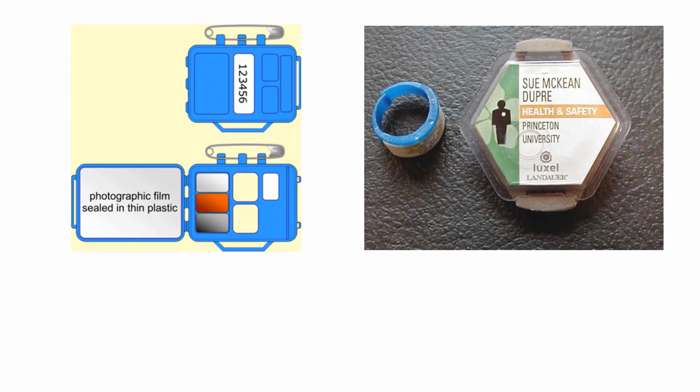Commonly in medical imaging, two badges are worn. For most techs, they will wear a normal dosimetry badge. Nuclear medicine techs, who work up different procedures using ionizing radiation as a radionuclide, will wear a ring badge as well because they are holding the radionuclide in a syringe in their hand. So we measure the amount of radiation that goes to the ring badge as well as the amount of whole body radiation that goes to the dosimeter on the chest.